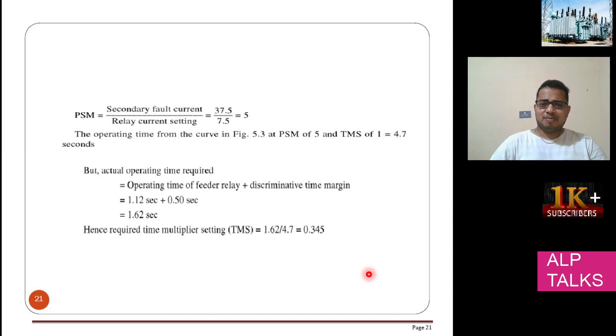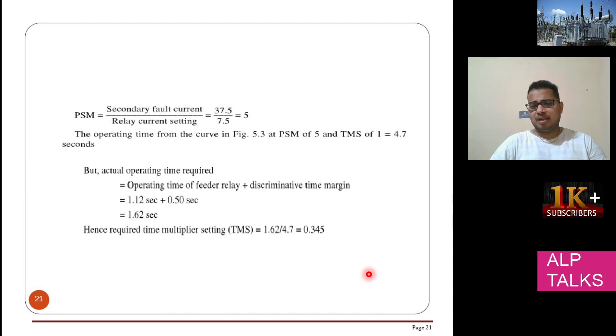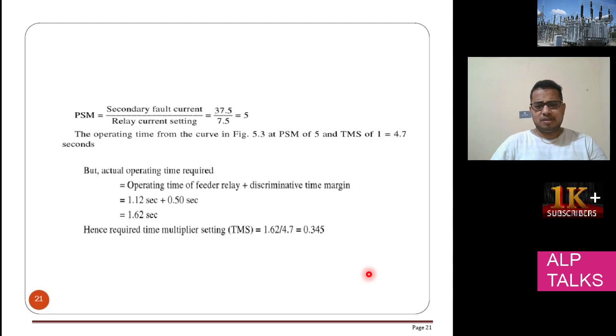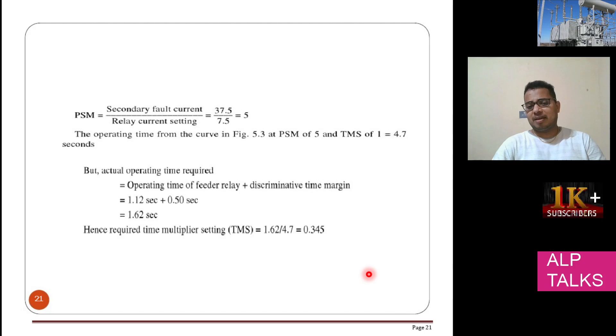The secondary fault current is 7500 / 200 = 37.5 amps. The relay setting at 150% is 7.5 amps, so PSM = 37.5 / 7.5 = 5. For PSM of 5 at TMS = 1, the operating time is 4.7 seconds. The discrimination time is 1.12 + 0.5 = 1.62 seconds. So TMS = 1.62 / 4.7 ≈ 0.34.